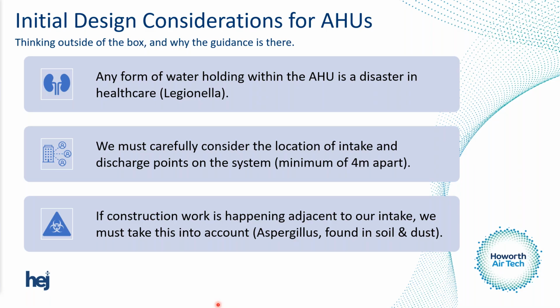We've got to carefully consider the location of intake and discharge points on the air handling unit. HTM says there's a minimum of 4 meters apart, but that's not the only thing to consider. We should also think about discharge points of other air handling units, LEV systems, helicopter pads if it's a big acute emergency hospital, and whether the intake section sits near the car park where a diesel wagon offloads food for 40 minutes every morning. These are things we need to consider as designers, validators, and authorized persons for Vent.